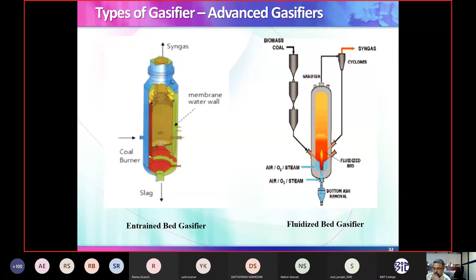The next one is a circulating fluidized bed gasifier. Here, whatever gas comes out is taken to the cyclone, all particles are removed, and it is taken back. This gives much better efficiency. Almost all the carbon in the ash is converted to gas, and you get only ash out, along with hot gas, which you can directly use in your boiler furnace or in a Brayton-based power plant, that is a gas turbine plant.